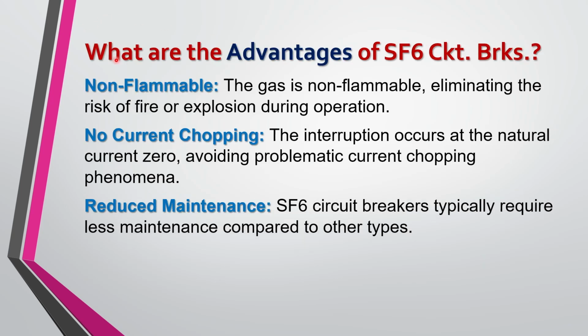Now let's explore what are the advantages of SF6 circuit breaker. Friends, you must have understood what the advantages are. So, non-flammable gas. SF6 is a non-flammable gas, eliminating the risk of fire or explosion during the operation of the circuit breaker. No current chopping. The interruption occurs at the natural current zero, avoiding problematic current chopping phenomena. So, this is self-explanatory as the contact separation is taking place at natural zero current, so it avoids any kind of current chopping phenomena. Reduced maintenance. SF6 circuit breakers typically require less maintenance compared to other types of circuit breakers.